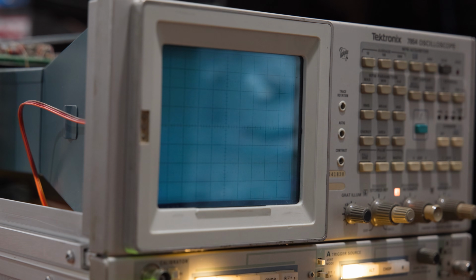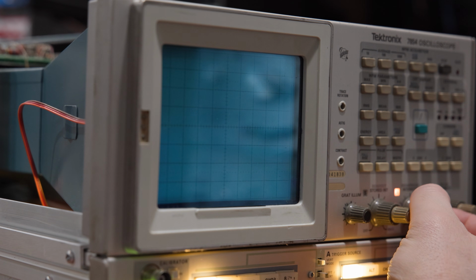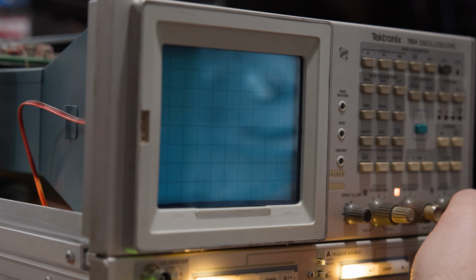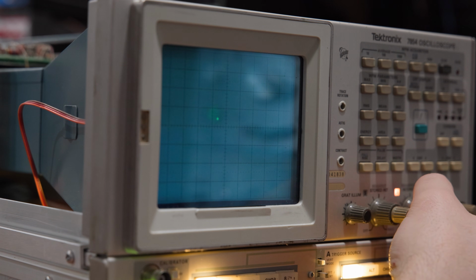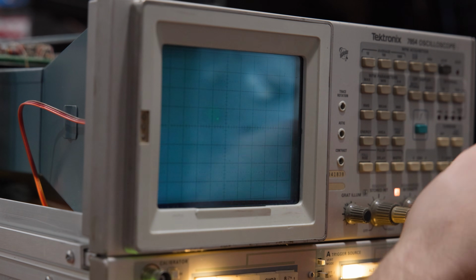All right, my grid bias is running a little bit low. This should extinguish the spot at 21.7 volts. So what we need to do is bump this up so we see it. There we go. Oh, that's coming up. So grid bias should just turn that spot off right there at 21 volts. It wasn't turning on until 29, so that should give us some more intensity on the tube, actually. Yeah, that right there is 22.5 for grid bias. So yeah, our grid bias was running a little light. That flashing is a dirty potentiometer. I have to fix that.